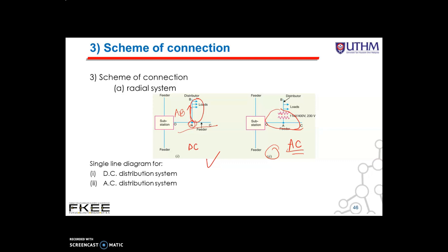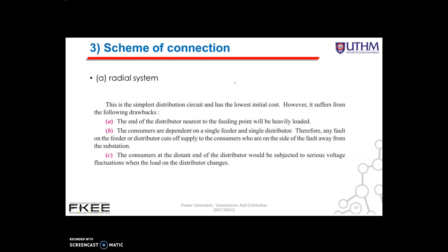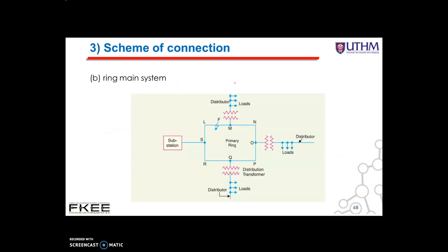The consumers are dependent on a single feeder and single distributor. Therefore, any fault on the feeder or distributor cuts off supply to consumers who are on the side of the fault away from the substation. The third drawback is that consumers at the distant end of the distributors would be subjected to serious voltage fluctuations when the load on the distributor changes. Due to these limitations, this system is used for short distances only.